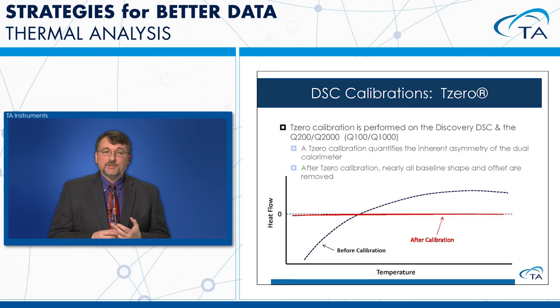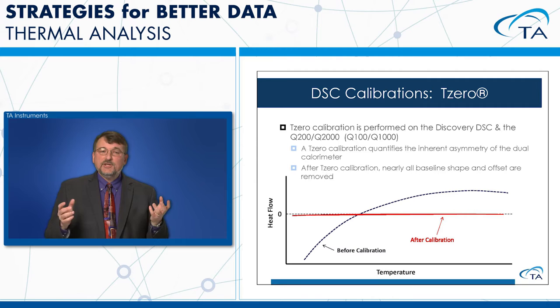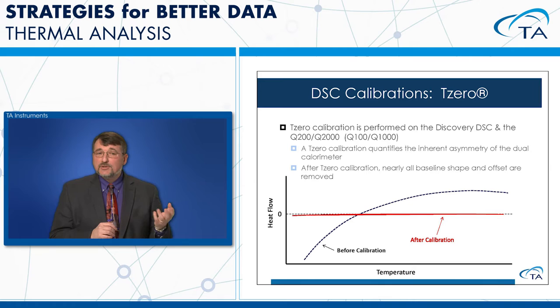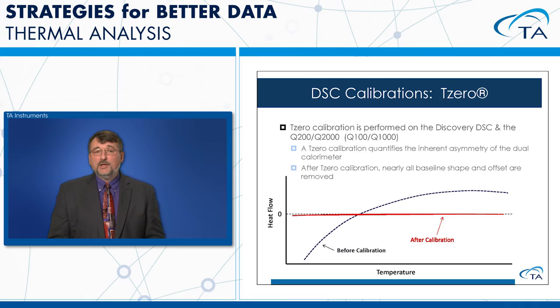The T0 calibration is not just a rotation or subtraction — it measures and quantifies any inherent asymmetry in the DSC cell, then compensates for that. Before calibration looks similar to other methods, but after T0 calibration the result is a flat line at zero. That's really what it should be: a flat line at zero for an instrument that's performing properly.